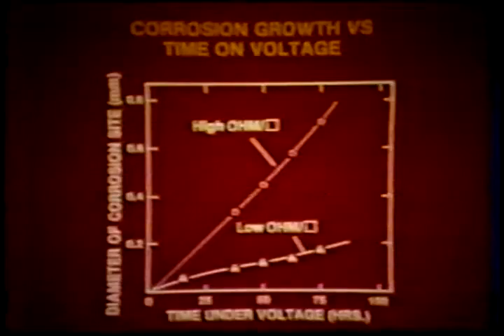It is interesting to note that these corrosion sites are almost perfectly circular in shape, which we believe is a result of the high field effects that occur on the outer edge of this capacitor. Here we see the diameter of a corrosion site, which is plotted as a function of time that our model capacitor is on test. We find that the corrosion grows at almost a linear rate. This suggests that the corrosion products are uniformly distributed over the entire surface area of the film. We also note that the growth rate is strongly dependent on the electrode thickness, or the resistivity.